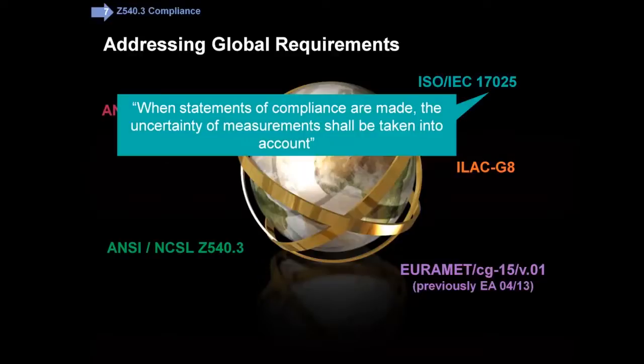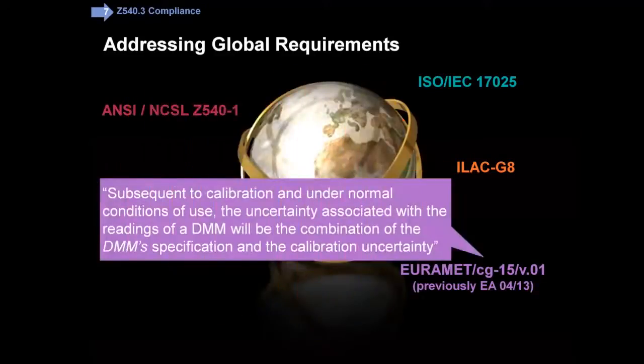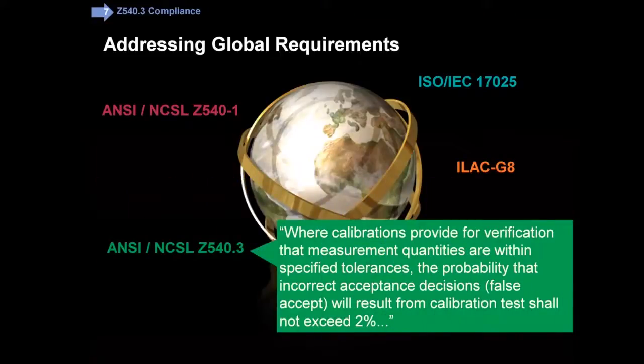Remember 17025 had that critical statement: when statements of compliance are made, the uncertainty shall be taken into account. One of the key documents for guidance on that was ILAC G8, which we looked at in depth in Module 5. Now on to the topic at hand — Z540.3. The standard itself is only 10 pages, but there's a single paragraph that almost swamps everything else in importance — the one shown in green. We're going to drill in and try to understand that one better.